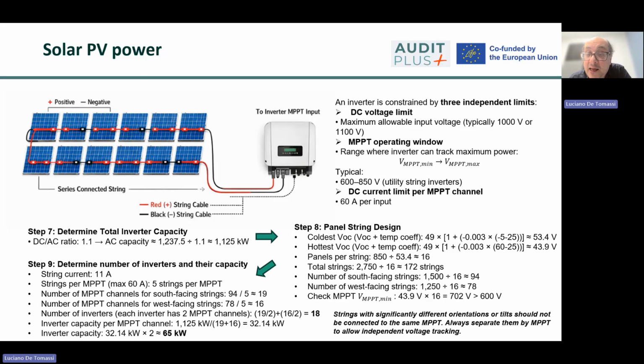An MPPT channel is an independent electrical input within the inverter that continuously optimizes the operating voltage and current of a connected PV string or group of strings so that it extracts the maximum possible power under changing conditions such as irradiance, temperature, and shading. Each MPPT channel operates separately, meaning it can track a different best operating point for PV arrays connected to it. This is important when different parts of a PV system experience different conditions.